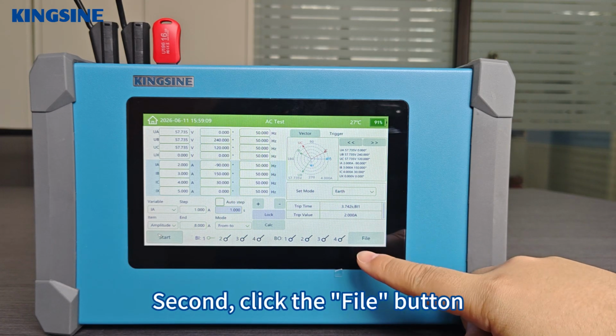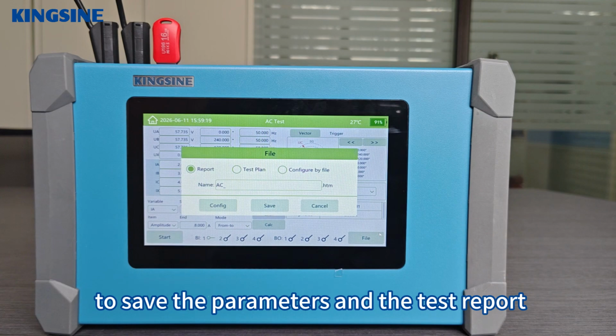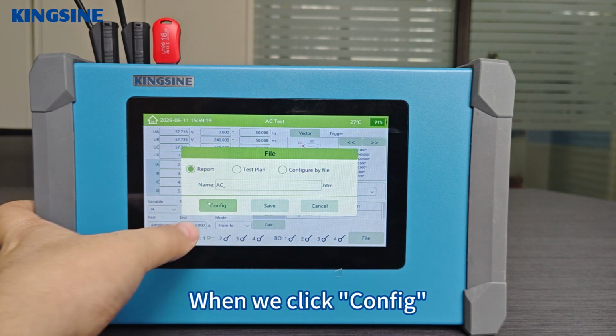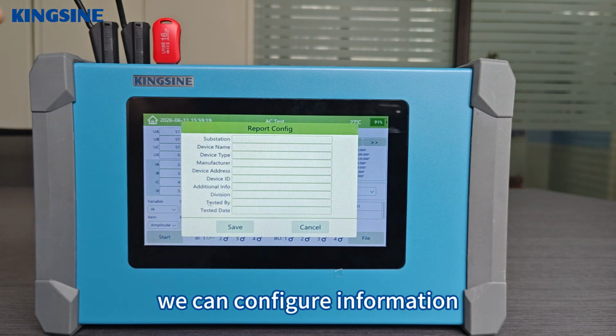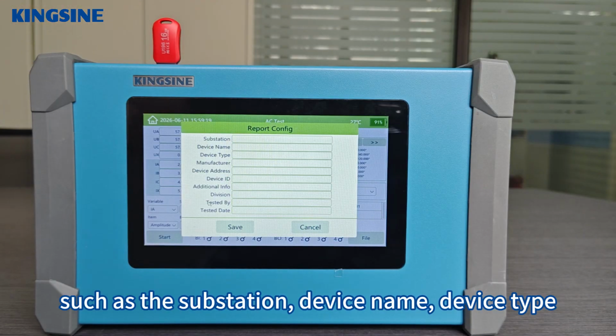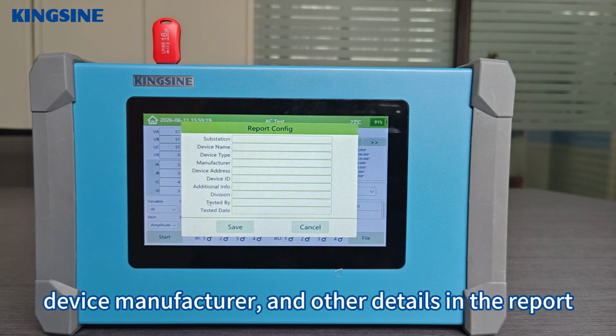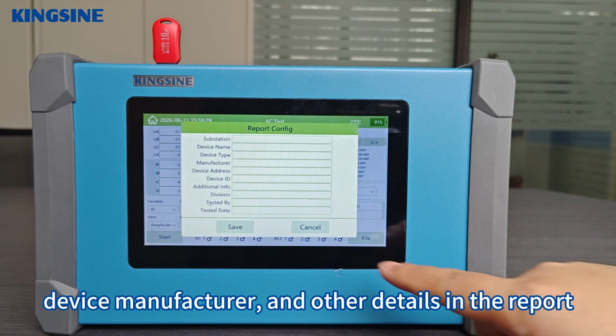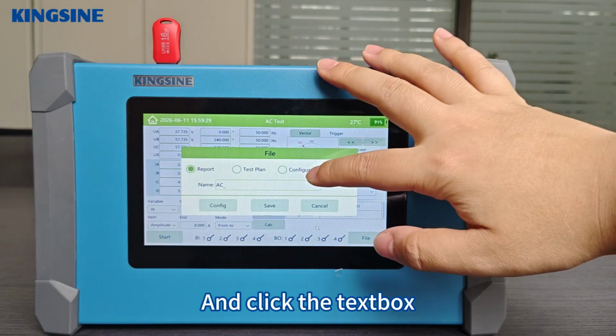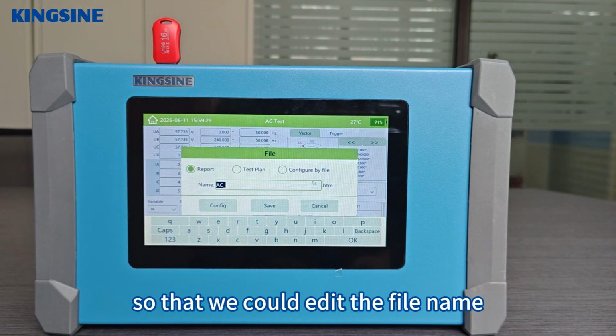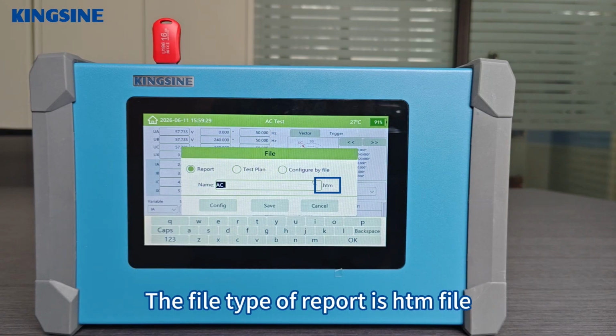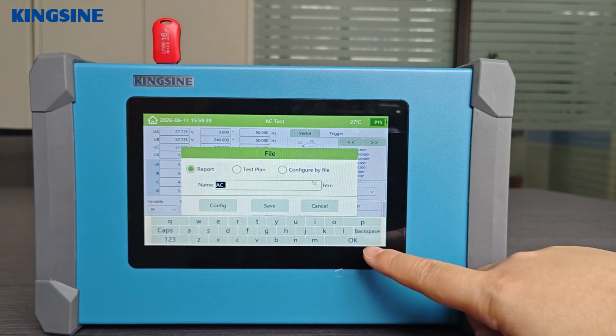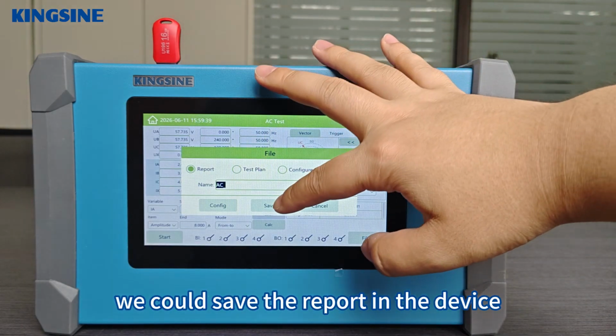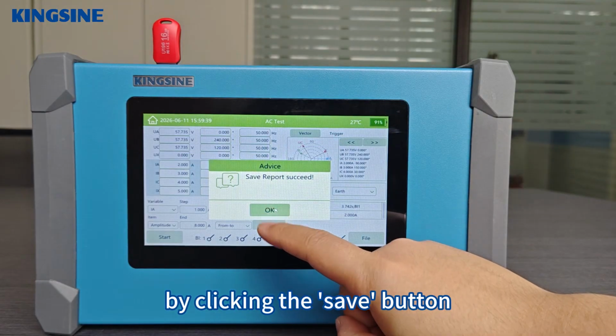Second, click the File button to save the parameters and the test report. When we click Config, we can configure information such as the substation, device name, device type, device manufacturer, and other details in the report. And click the text box so that we could edit the file name. The file type of report is HTML file. After editing, we could save the report in the device by clicking the Save button.